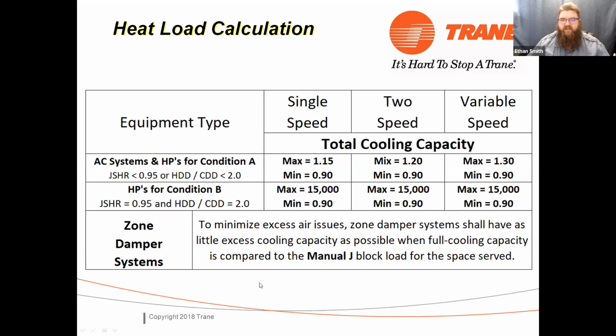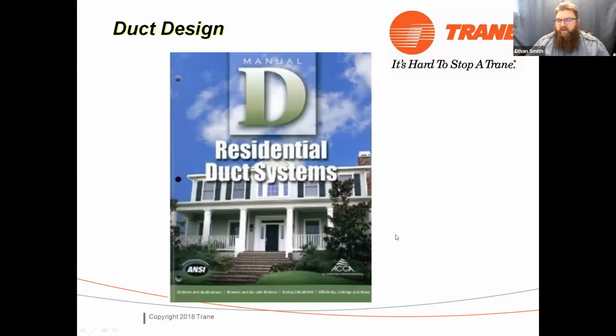Okay. Here's the big one down here, guys, though. To minimize excess air issues, zone damper systems shall have as little excess cooling capacity as possible when full cooling capacity is compared to the manual J block load. So when we say maximum, this is your upper limit. You don't want to be there. You'd much rather be down around 100% rather than being oversized, especially with zoning systems. Okay. Into that, we tie into our duct system as we talk about excess air. So excess air is where zoning lives or dies.